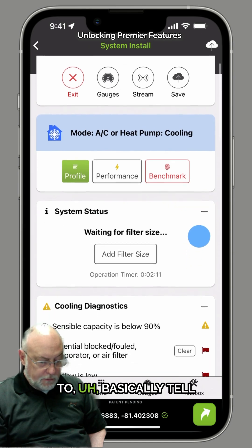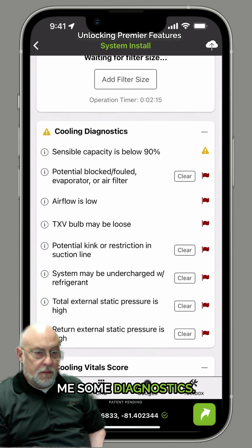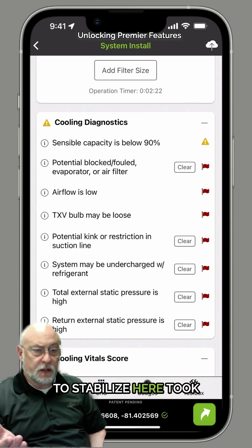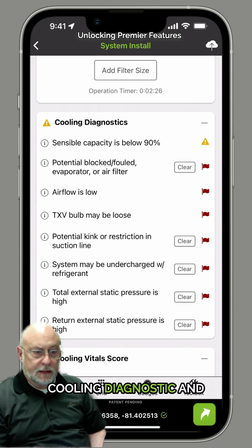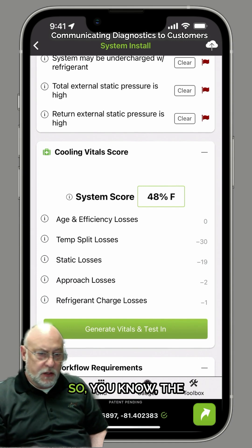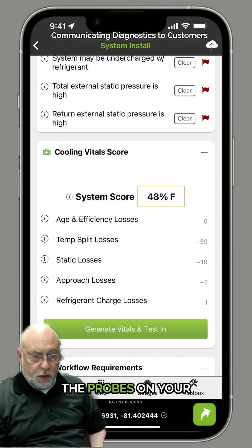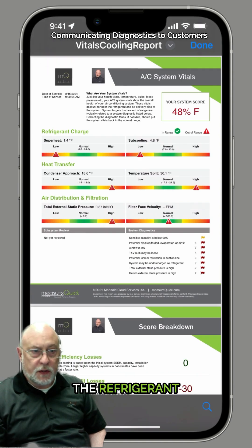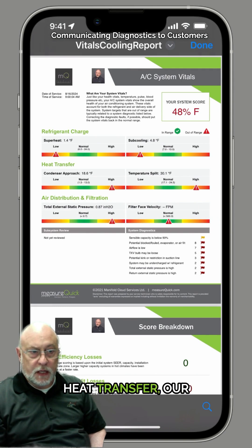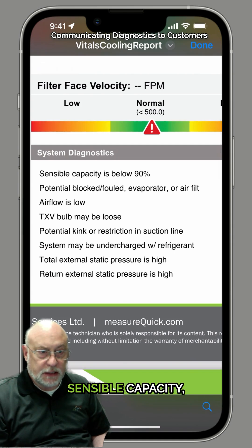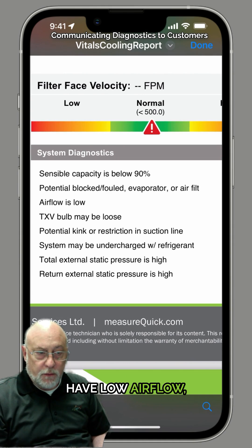It's going to tell me it's waiting for a filter size and give me some diagnostics. In the time it took the system to stabilize — literally the probes took a couple of minutes — I now have my full cooling diagnostic and can generate a report to help convey these issues to the customer. You can see our system is scoring at 48%. The story here is: we deployed the probes on your system, ran a scan, and right now your system is at 48%. Looks like we might have a problem with refrigerant charge, a problem with heat transfer — condenser approach is high, meaning the condenser is probably dirty. We have a temperature split issue, low sensible capacity, probably a dirty evaporator coil, low airflow, and high static pressure.